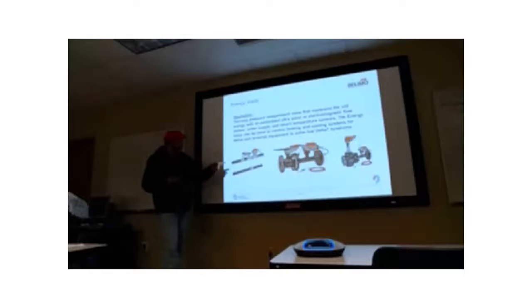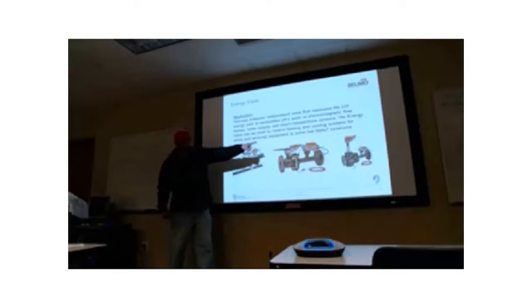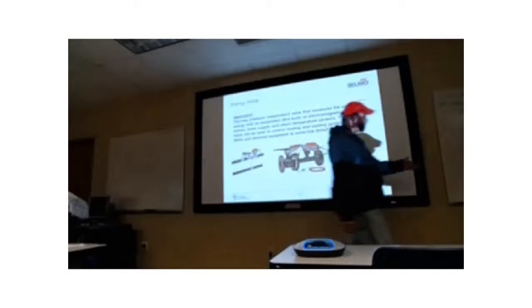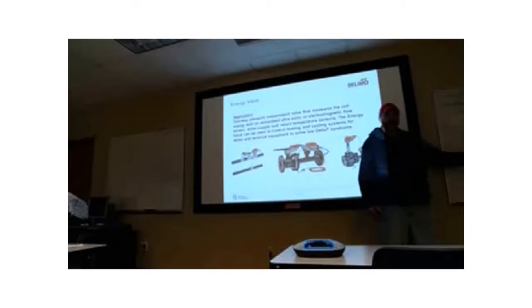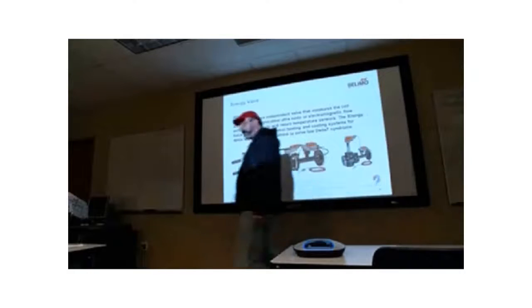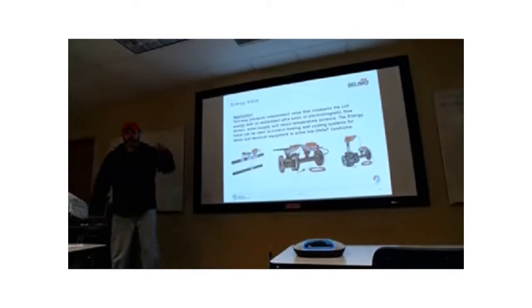So here's what I got here. In this case, here's a flow meter. That's an actual flow meter. Here's the valve. This is a closed loop flow control device, just like this, right? Remember I showed you this diagram here? It works just like that. It measures the flow, and it controls the flow to a set point.